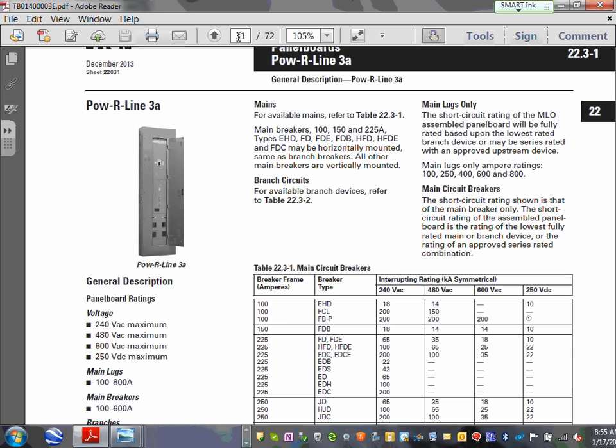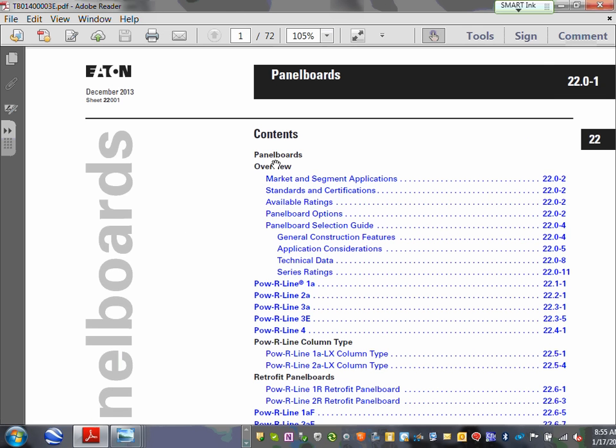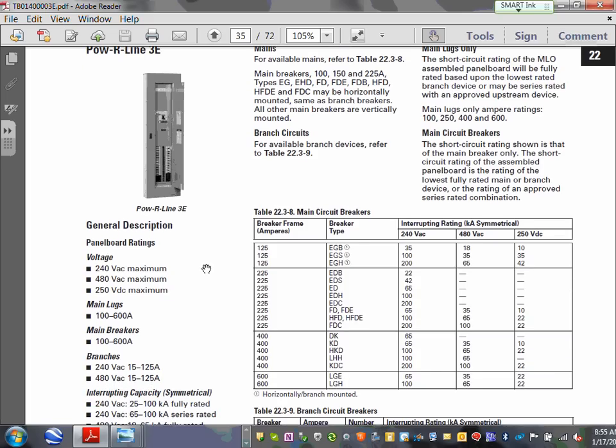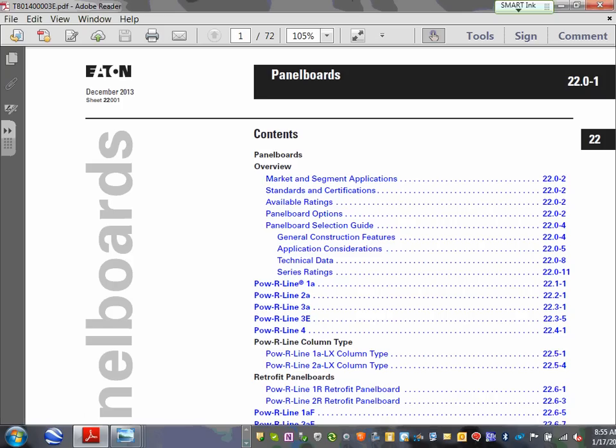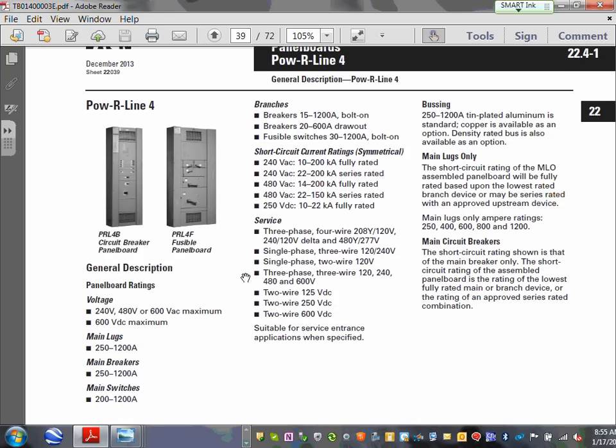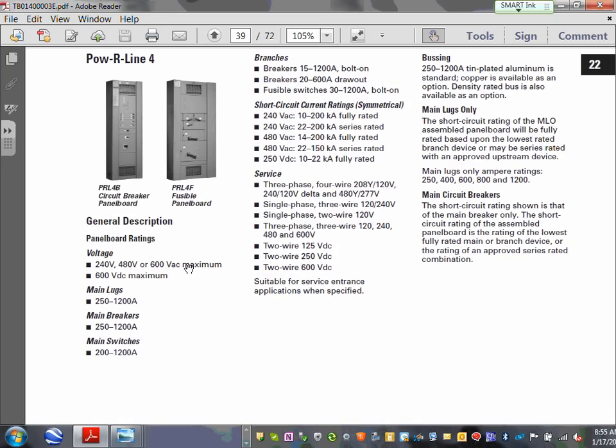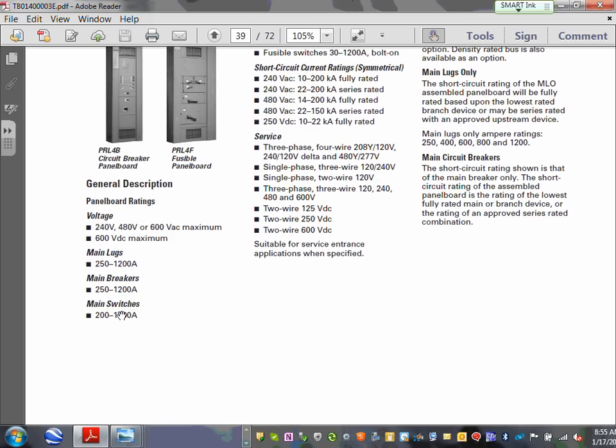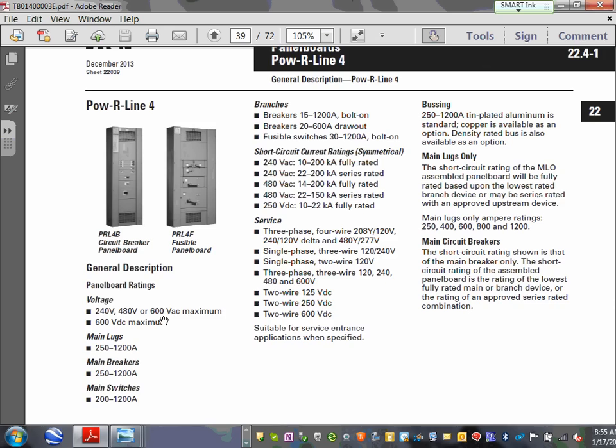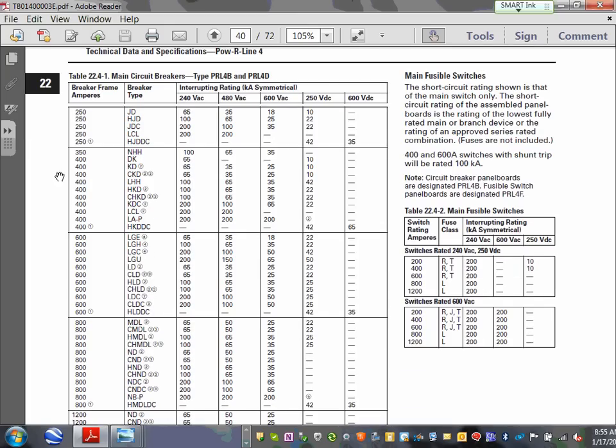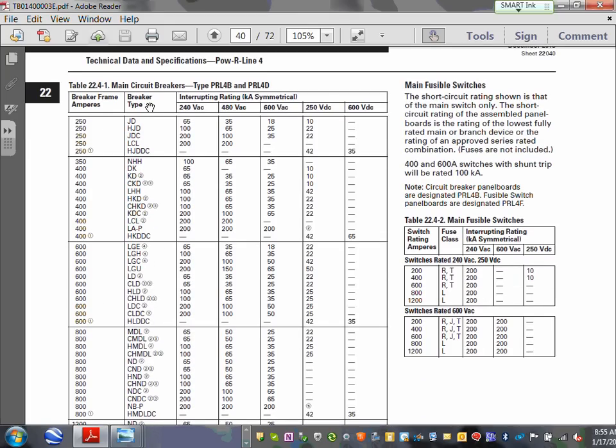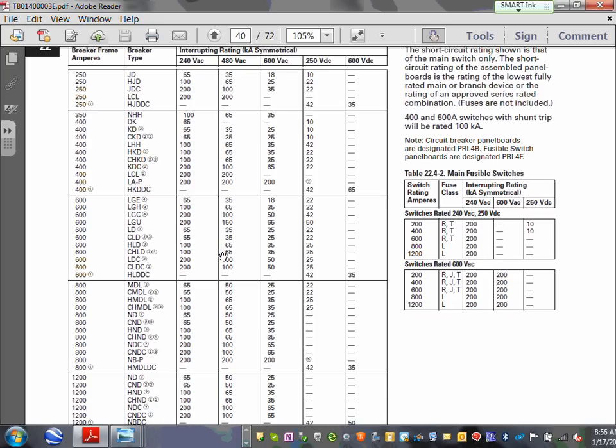These panels, and what happens if you need more amps? It keeps going up. Their last one is E. This can go up to, look at this. Oh, we were looking at that, didn't we? That 1200 amp. And if I go to 4, 4 is the largest. Look at the voltages. It covers every voltage that God created, and it can go up to, can you guys see that? 1200 amp. These panels, Adam, are going to be your mechanical panels in our project. So I showed you guys this is the cut sheets that you can get. It gives you a lot of details, obviously, the circuit breakers. Look at the type of feed, breaker frame size, breaker type, interrupting rating, and different voltages. It gets a little bit involved.